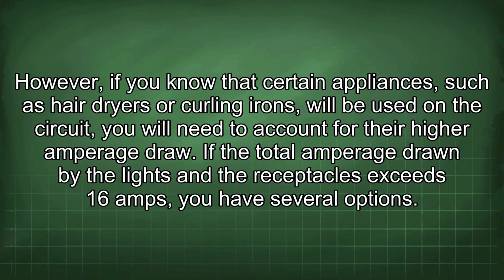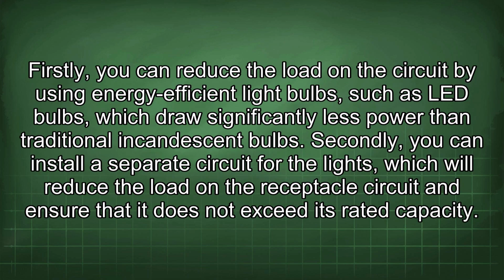However, if you know that certain appliances, such as hairdryers or curling irons, will be used in the circuit, you will need to account for their higher amperage draw. If the total amperage drawn by the lights and the receptacles exceeds 16 amps, you have several options. Firstly, you can reduce the load on the circuit by using energy-efficient light bulbs such as LED bulbs, which draw significantly less power than traditional incandescent bulbs.